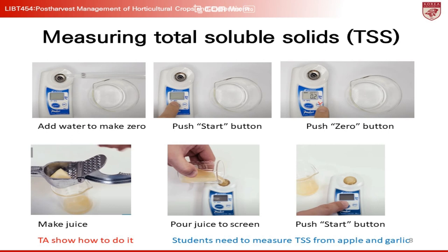This step compensates for any background solution and ensures accuracy in your subsequent measurements. After calibration, you're ready to measure your actual sample. Thoroughly clean the prism surface to remove the water used for calibration. Then, place a few drops of the juice or solution you're testing onto the prism, close the cover plate, and press the Start button. The refractometer will display the TSS in degrees Brix, which is a scale that indicates the amount of sucrose or soluble solids present in 100 grams of solution.